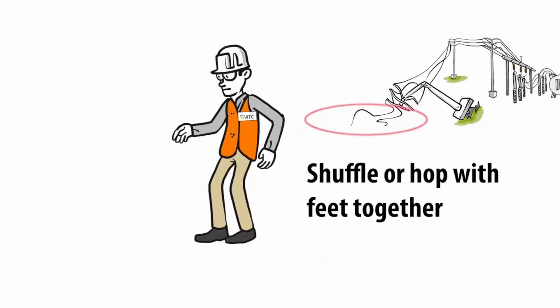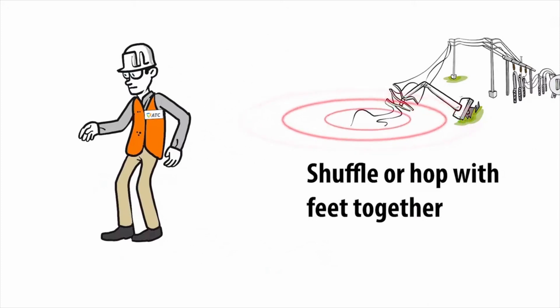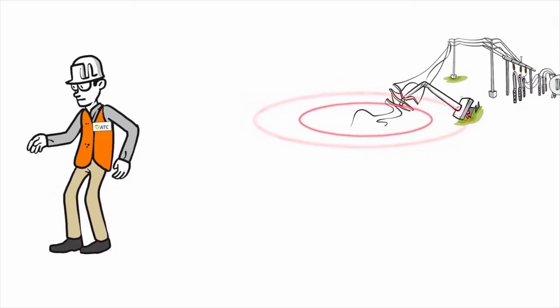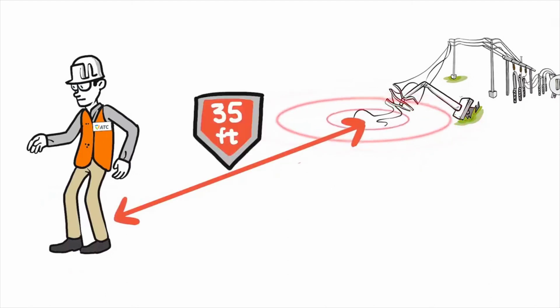So, shuffle your feet or hop with both feet at the same time to avoid electrocution. The very best practice is to stay at least 35 feet from any downed power source.